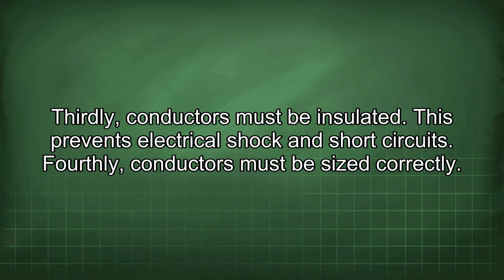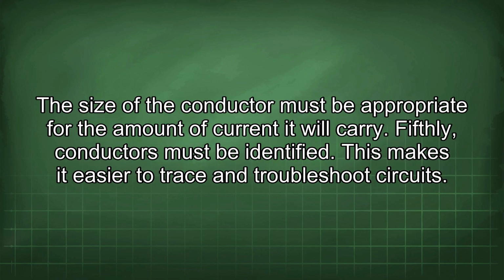Thirdly, conductors must be insulated. This prevents electrical shock and short circuits. Fourthly, conductors must be sized correctly. The size of the conductor must be appropriate for the amount of current it will carry. Fifthly, conductors must be identified. This makes it easier to trace and troubleshoot circuits.